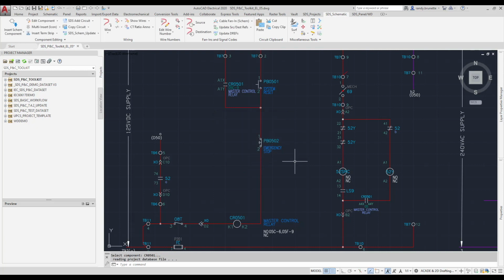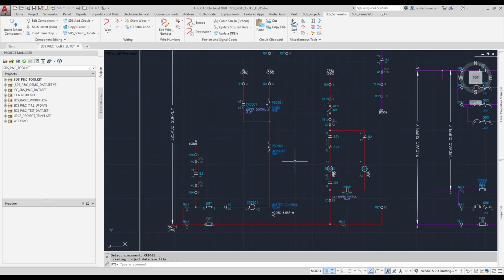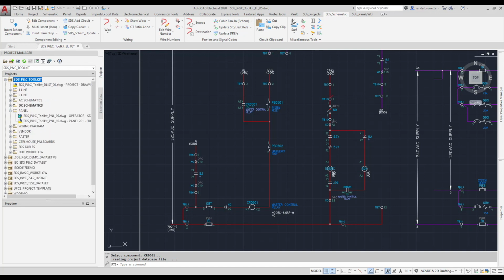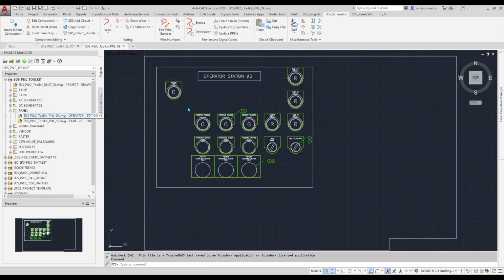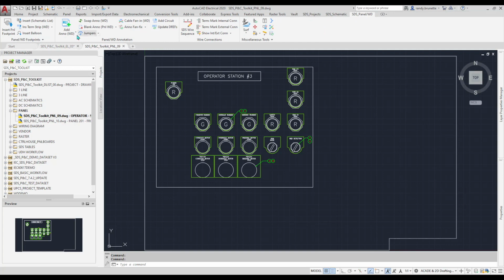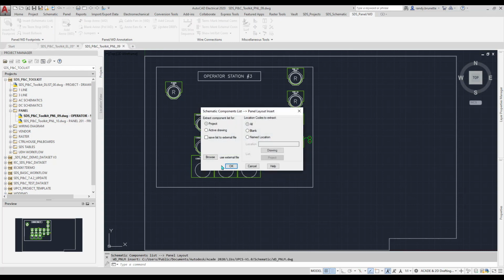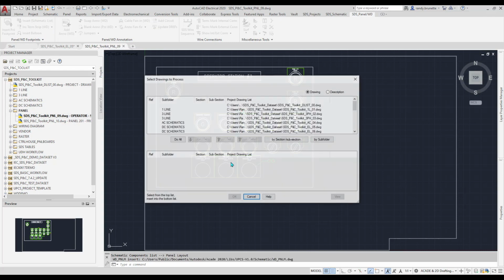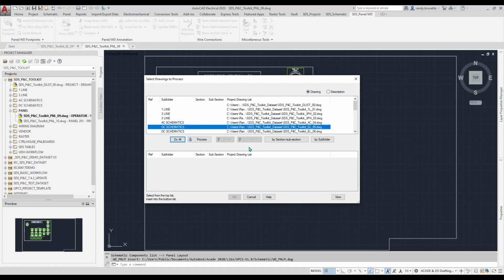Now that we have the information in our schematic, the next step is to reuse that information again and again. In the example here, we'll go to the panel drawing and insert these two push buttons, PB0501 and 0502, reusing existing information from the schematic drawings. Here is the example. We'll move to the panel tab, select on Insert Schematic List, and select from the project, because we want to get the information from a drawing that's not the current drawing.